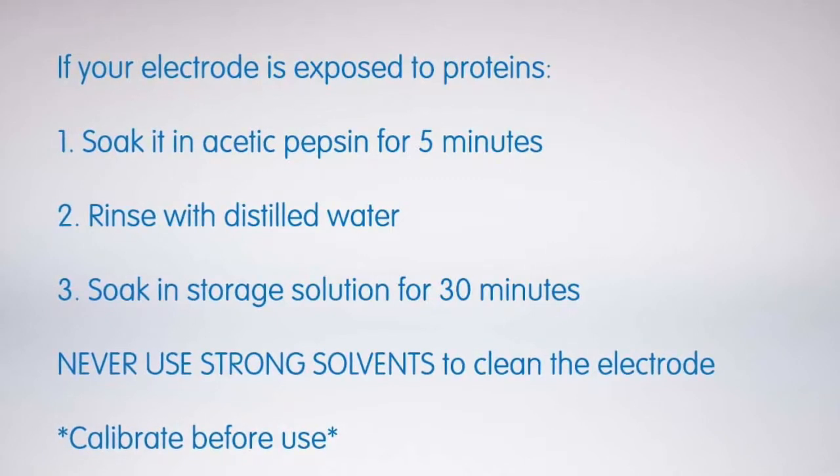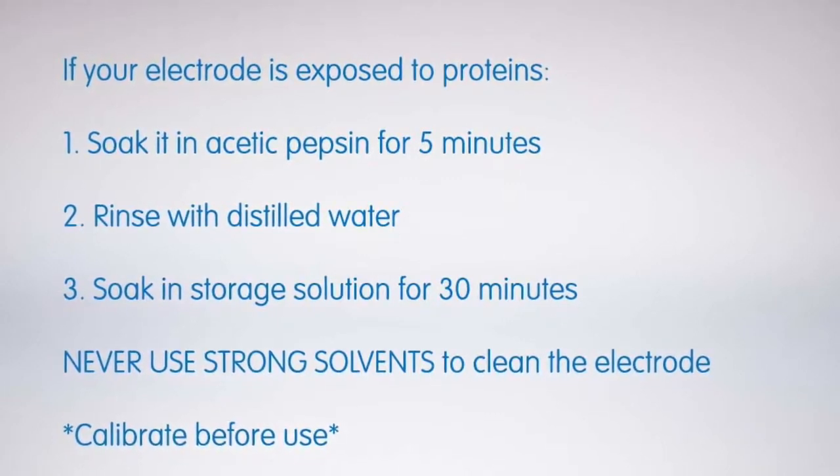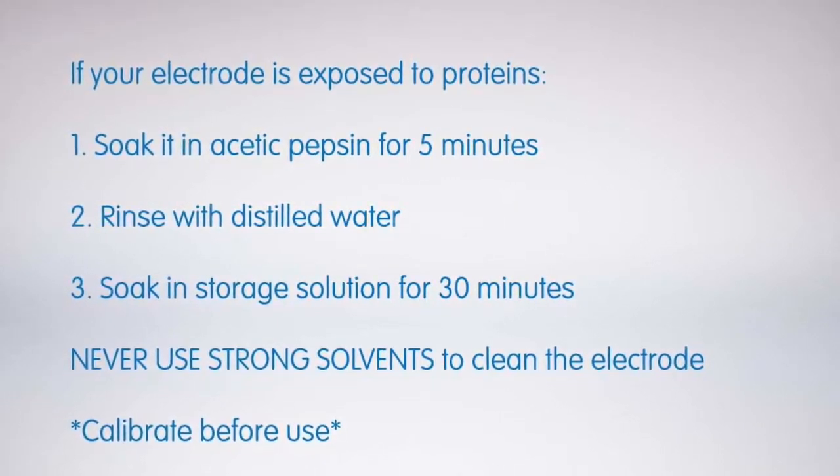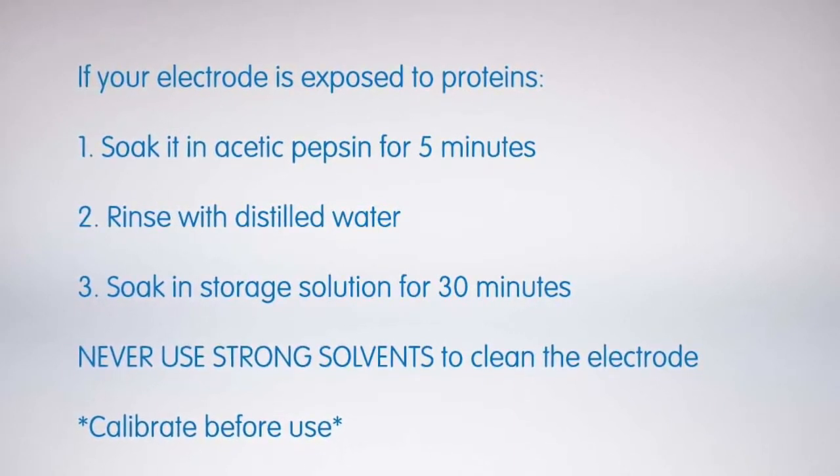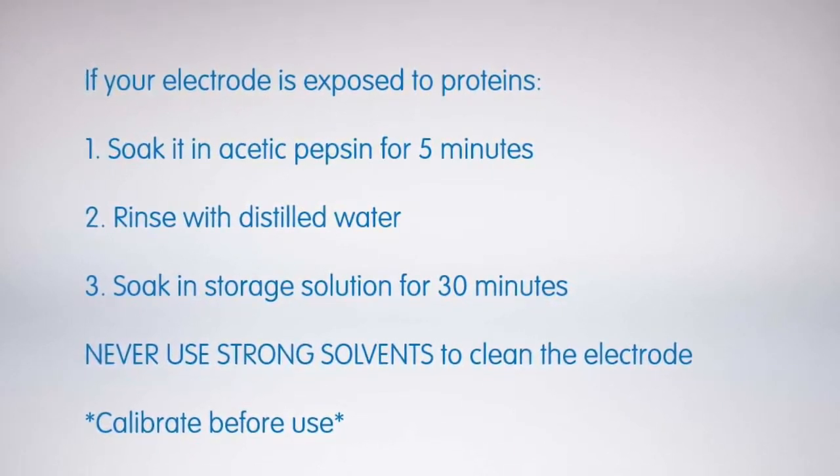If your electrode is exposed to proteins, soak it in acidic pepsin for five minutes. Rinse with distilled water. Then soak in storage solution for at least half an hour.